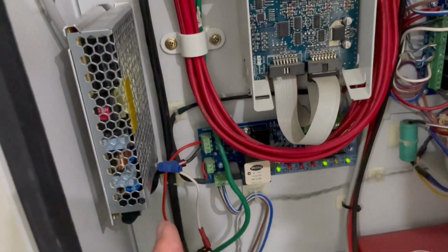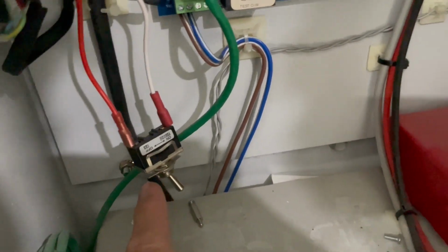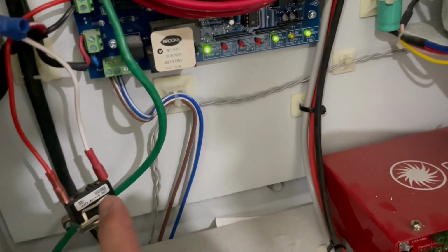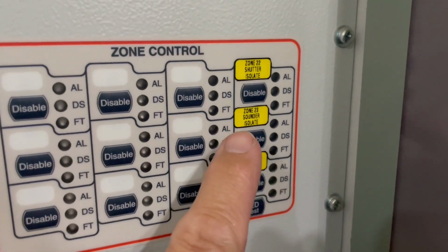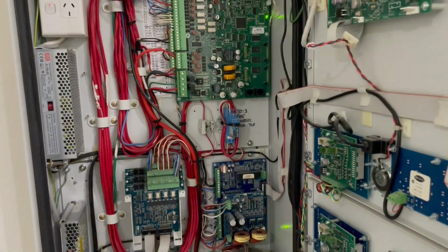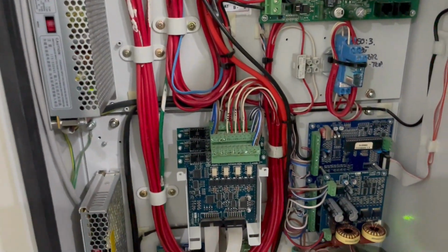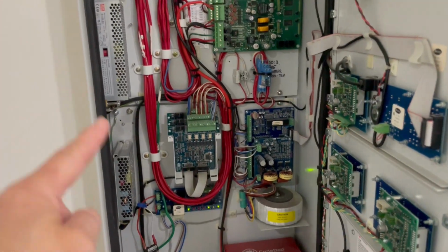Okay? So I said, if I want to reboot this, I have to shut down the whole system. So I installed one switch, because it had happened before that I only needed to reboot this instead of the main fire indicating panel. Why should I avoid rebooting or switching it off? Because we have a roller shutter in the building, so we have to avoid shutting it down. That means if I switch that off, I have to go down in the basement and put a cable tie on the roller shutter so it will not drop in case I switch off the system.